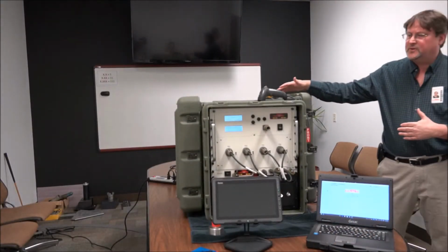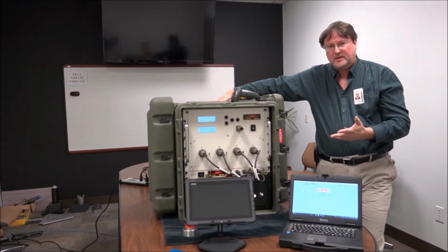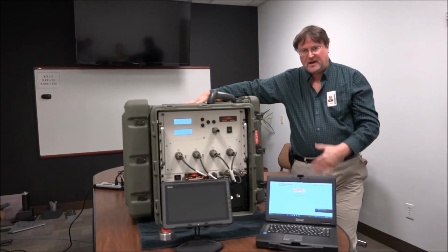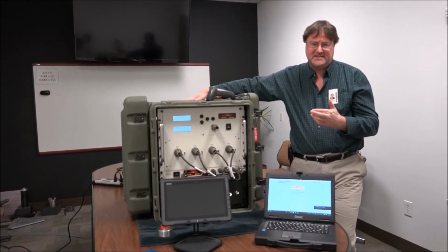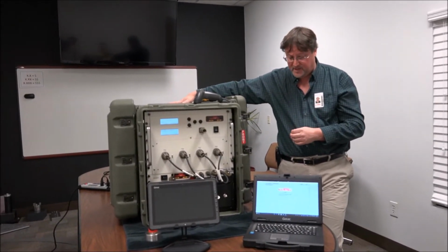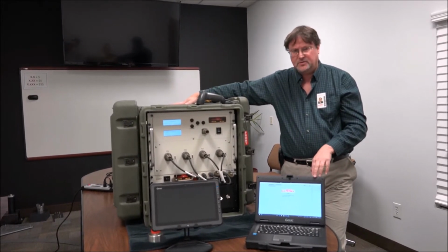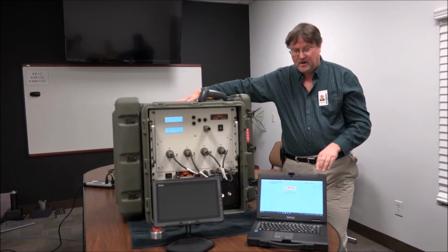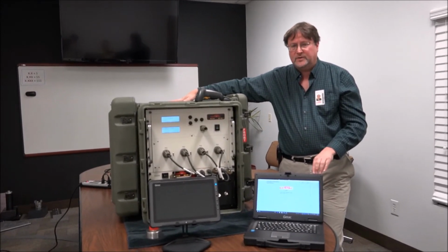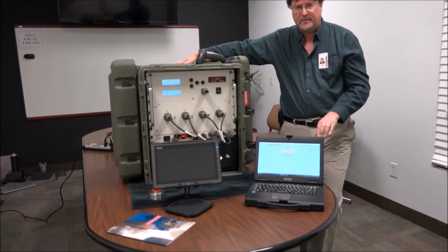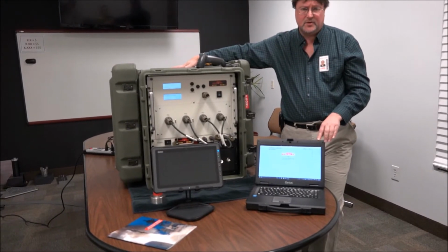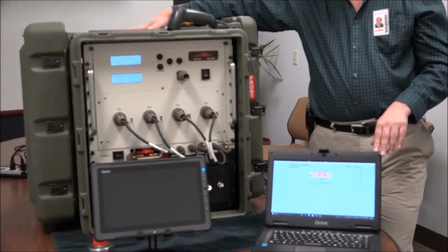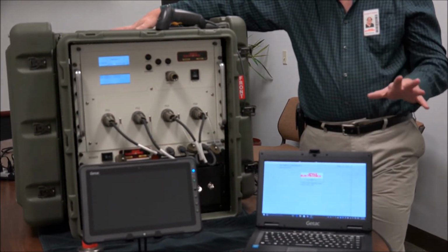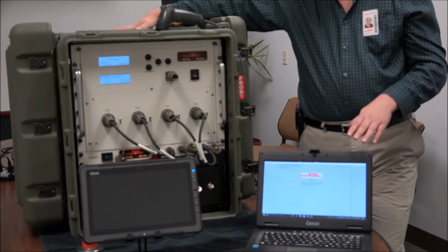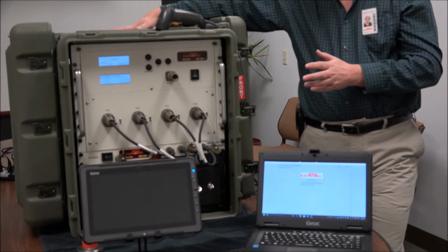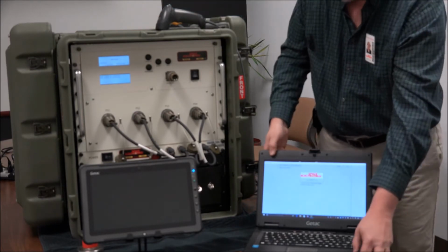So let's talk about software and integration for a moment. We provide or we sell software that will run the system. That software allows you as an engineer to define almost everything about a test sequence that you are performing or your operators are performing. You can also integrate this software into your own software by using our app DLL or our low-level communication DLL. Both of those are written in C#. Or you can interface it directly through the serial port and use the serial command structure to communicate with the meter. So any one of those application methods allows you to communicate with the meter and shed as much of the software development as you might desire. We'll show you demonstrations with our software.